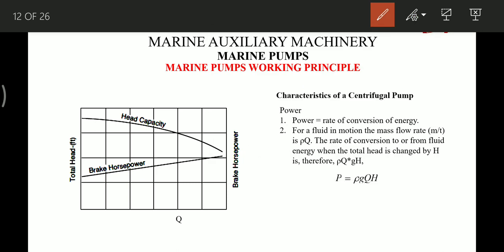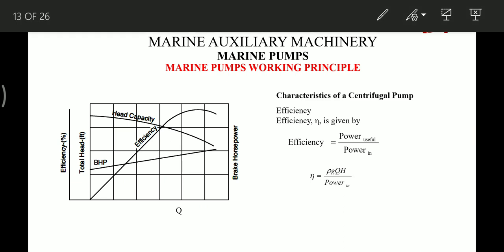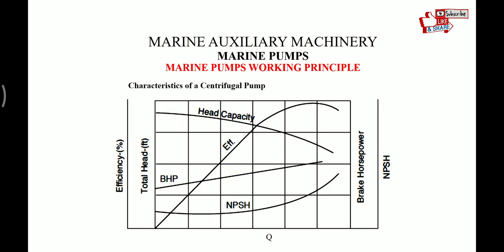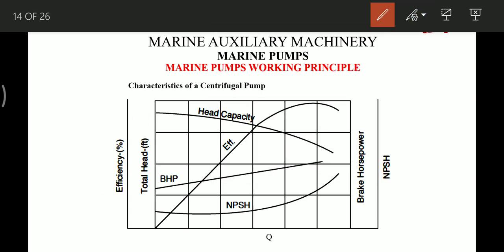In the same graph we can incorporate the power curve, with formula P = ρgQH, and the efficiency curve, with equation η = ρgQH / total power input. The final graph for the centrifugal pump characteristic shows the head curve, efficiency curve, brake horsepower (power) curve, and the NPSH (net positive suction head) curve. NPSH will be discussed in detail in an upcoming video as it requires more attention.